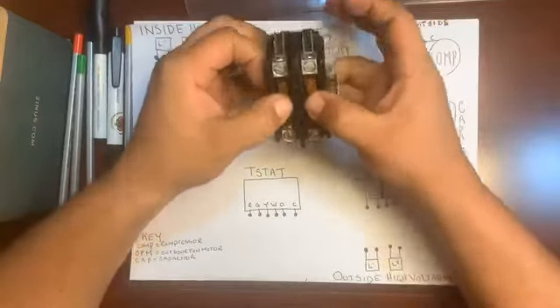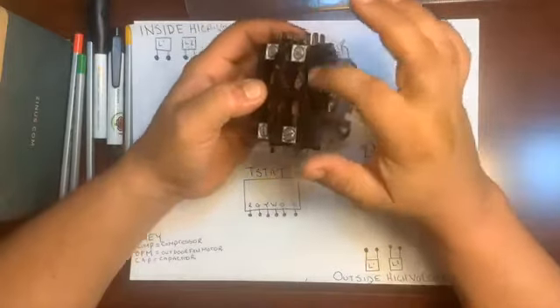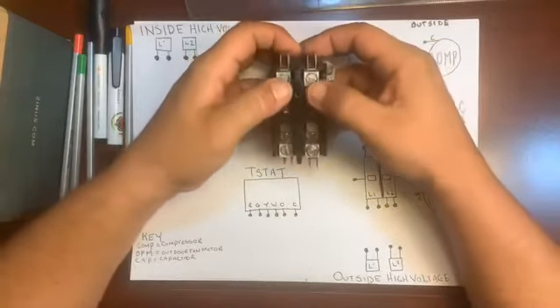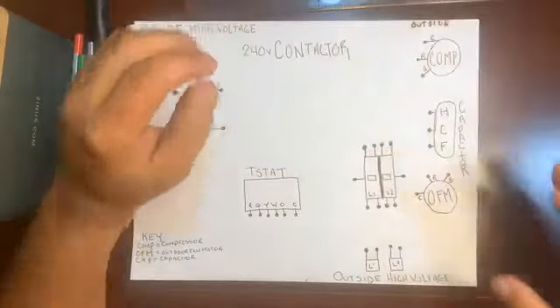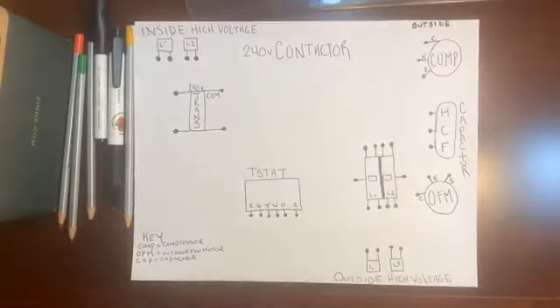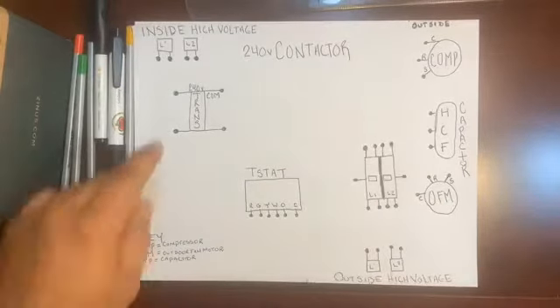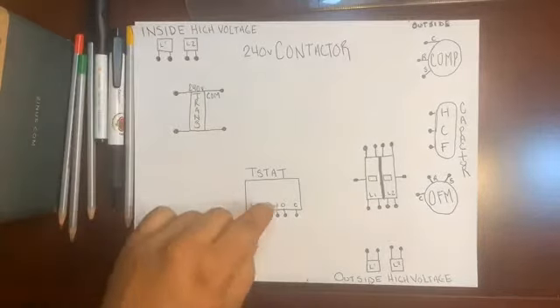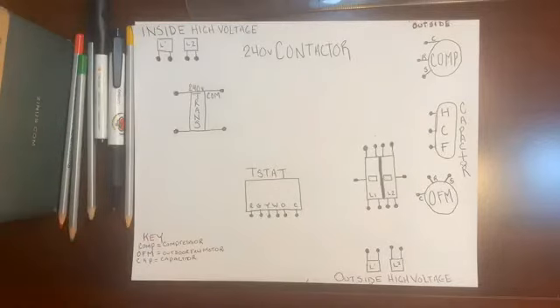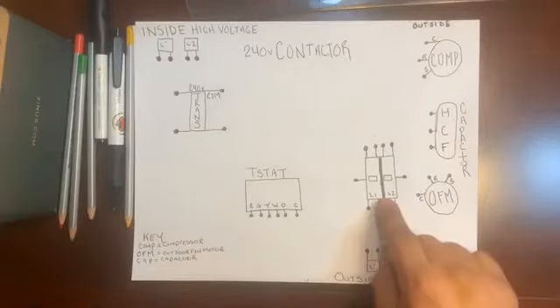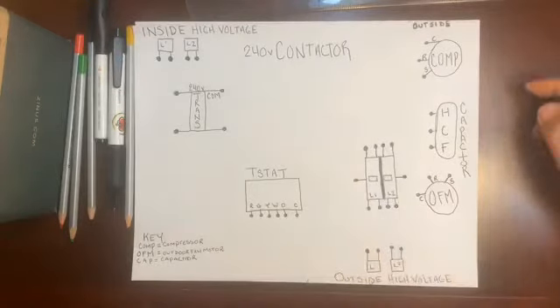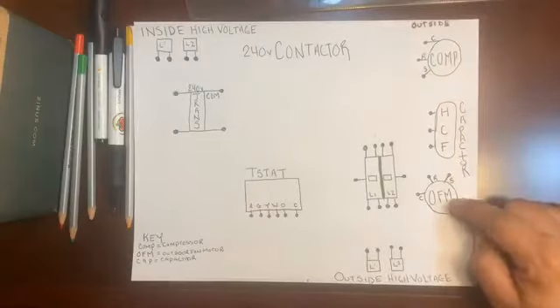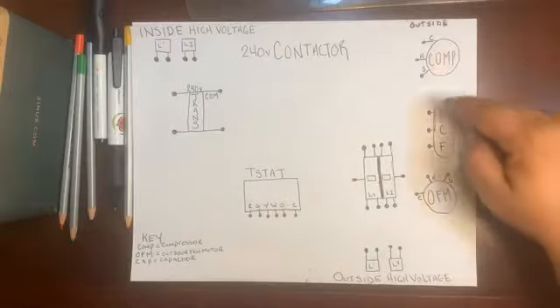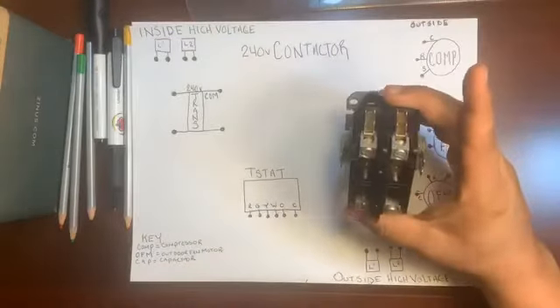So quick recap, we get 24 volts on the sides here, and that's what drops the plunger and completes the circuit. There's a center bar that runs down the middle of the contactor that separates 120 volts through this and 120 volts through this channel for a total of 240 volts. Today on the diagram, we're going to split it to show what's inside and what's outside. So we're gonna look at the components real quick. Our inside high voltage, line 1, line 2, our transformer, our thermostat, all components that go inside the home, inside the air handler. On the other side here, we're gonna see the compressor contactor, which we discussed is in the condenser. Then we're gonna have our compressor, our outdoor fan motor that goes on top of the compressor, and our capacitor, and how these three connect into the 240 volt contactor.